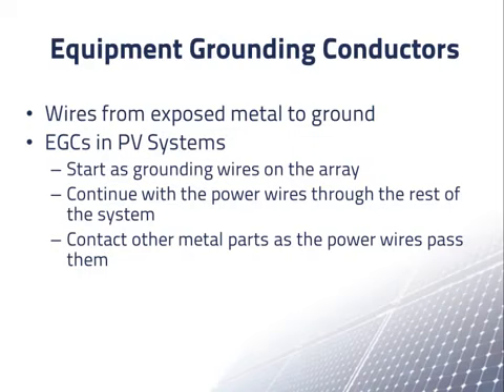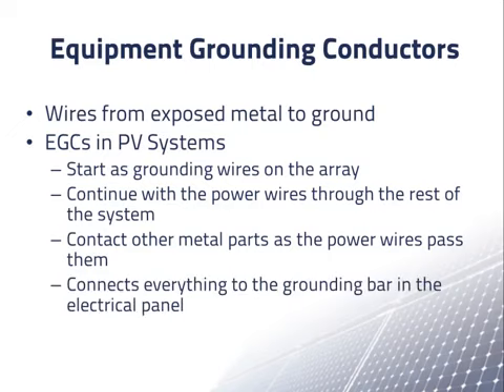Eventually, the equipment grounding conductors from the array are connected to a grounding junction in the inverter. When the inverter is connected to an electrical panel, the link includes a grounding wire that connects the grounding junctions in the inverter and the panel. Through these connections, all of the equipment grounding conductors are connected to the electrical panel's ground, and from there to the grounding rod. There may also be a direct connection between the array or inverter and a grounding rod, as we'll soon discuss.